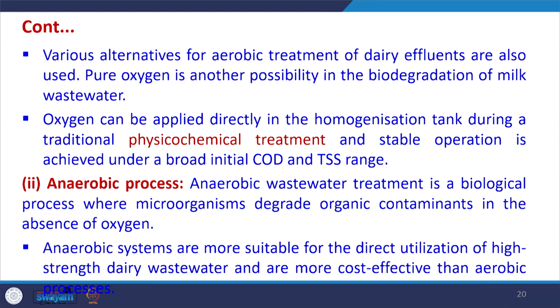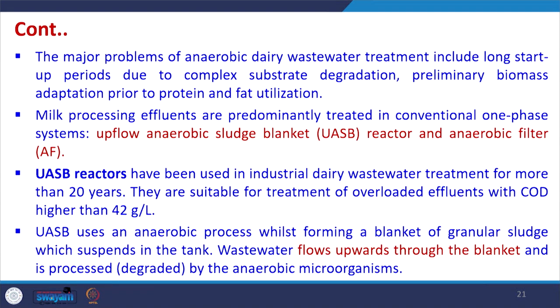Anaerobic processes can also be adopted for treatment of dairy wastewater. In anaerobic wastewater treatment, microorganisms degrade organic contaminants in the absence of oxygen. Anaerobic systems are more suitable for direct utilization of high-strength dairy wastewater and are more cost-effective than aerobic methods. The major problems associated with anaerobic treatment include long start-up periods due to acclimatization and the need for preliminary biomass adaptation prior to protein and fat utilization.